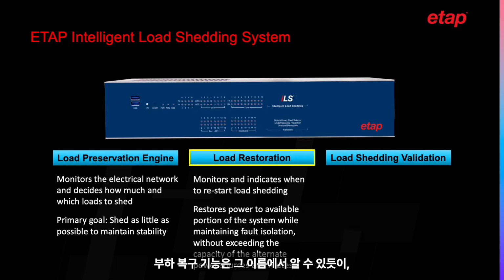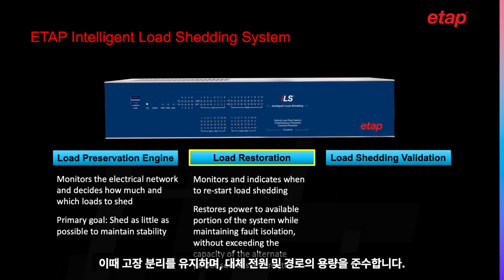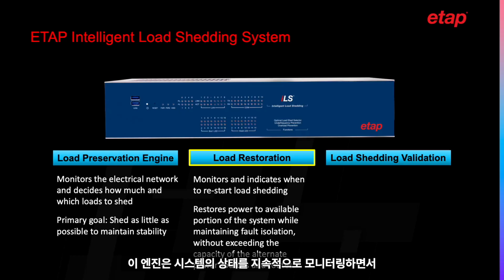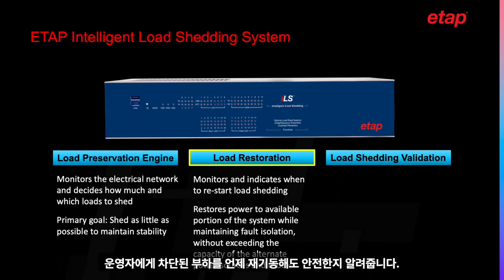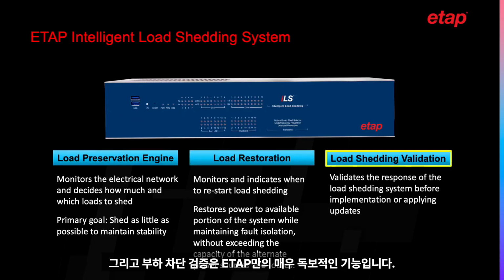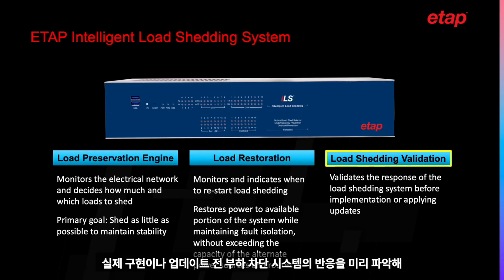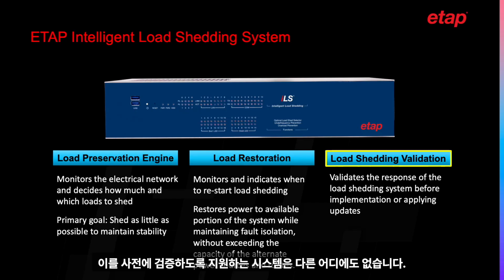The load restoration function, as the name implies, restores power to the available portion of the system while maintaining fault isolation without exceeding the capacity of the alternate power sources and routes. This is the engine that monitors the system and indicates to the operator when it is okay to restart shed loads. And load shedding validation is a very unique feature of ETAP. There is no other load shedding system that can allow the user to validate the response of their load shedding system before getting implemented or performing updates.